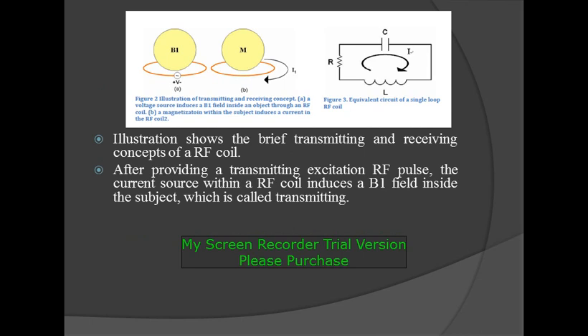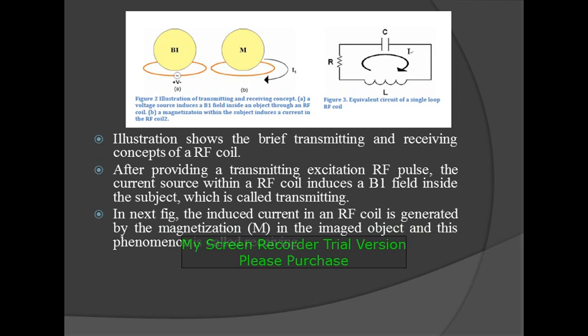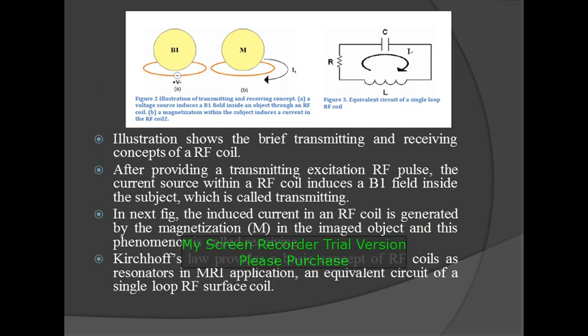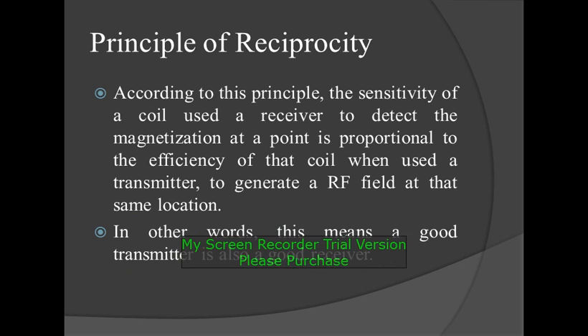This illustration shows the brief transmitting and receiving concept of an RF coil. After providing a transmitting excitation RF pulse, the current source within an RF coil induces a B1 field inside the subject — this is called transmitting. In the next figure, the induced current in an RF coil is generated by the magnetization in the image subject, and this phenomenon is called receiving. Kirchhoff's law provides a basic concept of RF coils as resonators in MRI application, showing an equivalent circuit of a single-loop RF surface coil.